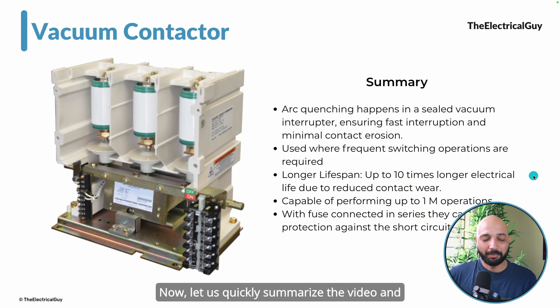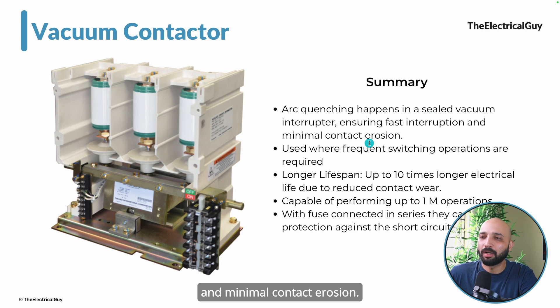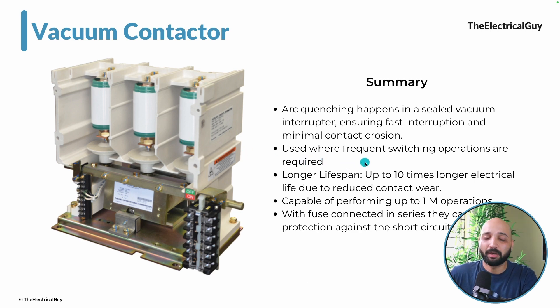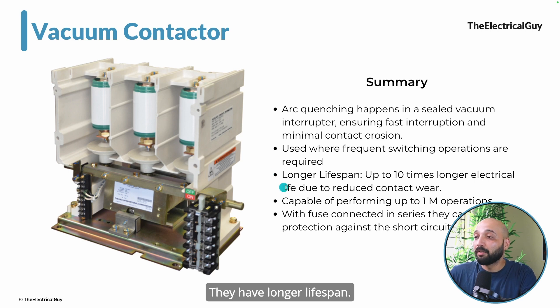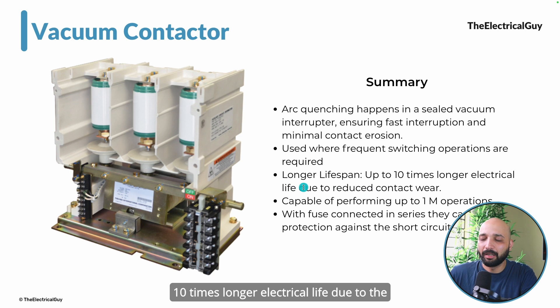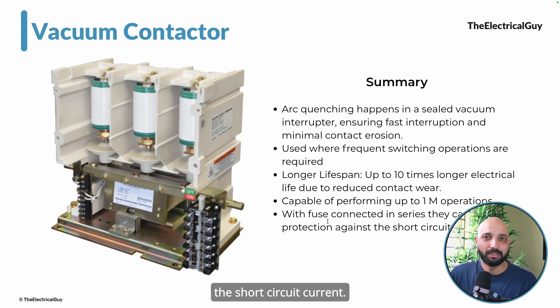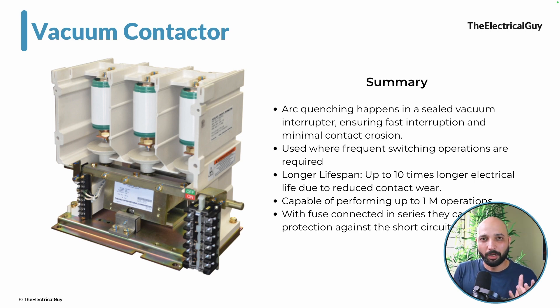To summarize: arc quenching in a sealed vacuum interrupter ensures fast interruption and minimal contact erosion, making vacuum contactors highly capable for high switching operations — up to 1 million operations. They are used wherever frequent switching is required: motor switching, power distribution loads, arc furnaces, and more. They have a lifespan up to 10 times longer than alternatives due to reduced contact wear. With a fuse in series, they can also provide short circuit protection. Remember: vacuum circuit breakers and vacuum contactors are two different devices and cannot replace each other.